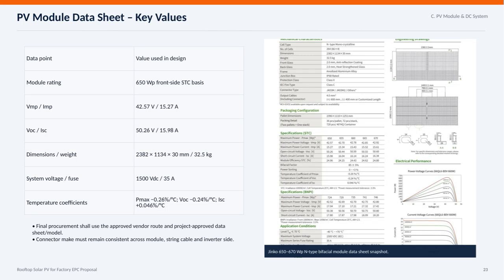Here we have a detailed snapshot of the key values from the PV module datasheet for the Jinko 650 to 670 Watt N-type bifacial module. These values form the basis of our design and are critical for understanding the system's performance. Starting with the module rating, it's rated at 650 watts peak on the front side under standard test conditions. The maximum power voltage and current are 42.57 volts and 15.27 amps respectively, while the open circuit voltage stands at 50.26 volts and the short circuit current at 15.98 amps. The physical dimensions of the module are 2,382 by 1134 by 30 millimeters with a weight of 32.5 kilograms. Our system voltage is set at 1,500 volts DC, paired with a 35 amp fuse for protection.